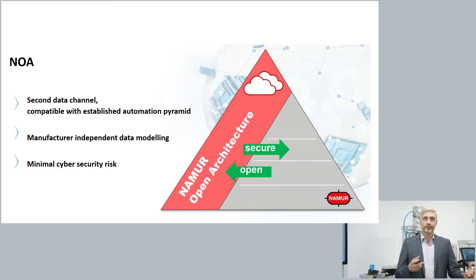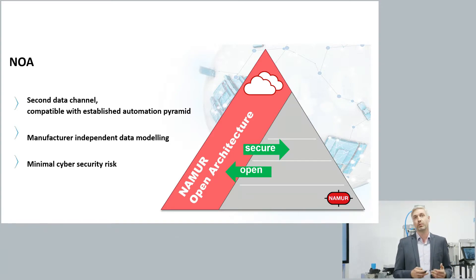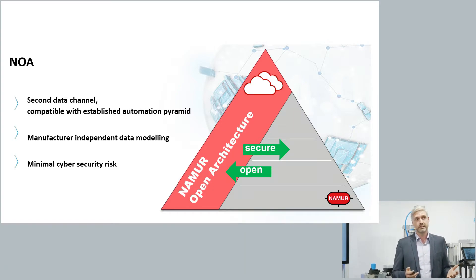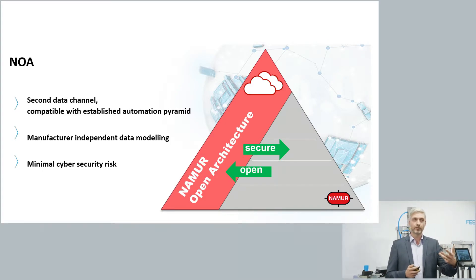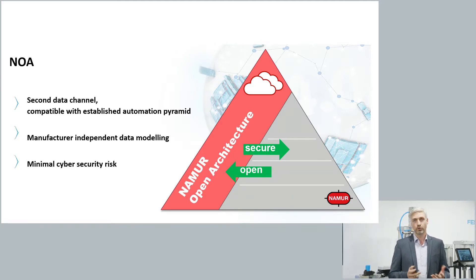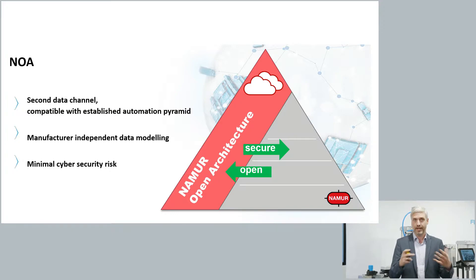One reason for the separation is that the changes needed in your core process control are very minimal, sticking to what is already established — making NOA very compatible for brownfield applications and existing plants, which is the explicit target of NOA. Another reason is that handling large amounts of data is simply cheaper in an IT environment compared to the OT equipment in your core process control area.